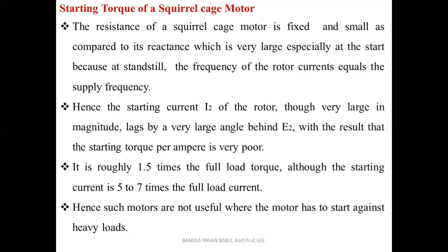Or in the theoretical case, it will be less than somewhat 90 degrees, but there is a lot of lagging. So obviously, cos 90 is not practically possible. The rotor never rotates, but the amount of current drawn will be very high, which, if continued in a practical session, may damage the windings.